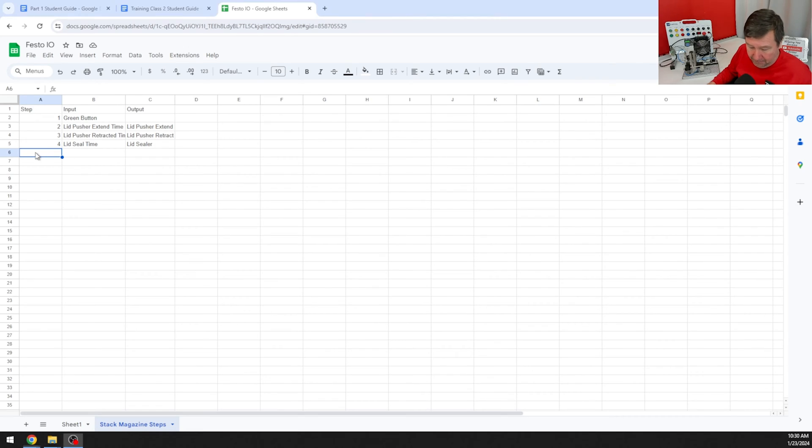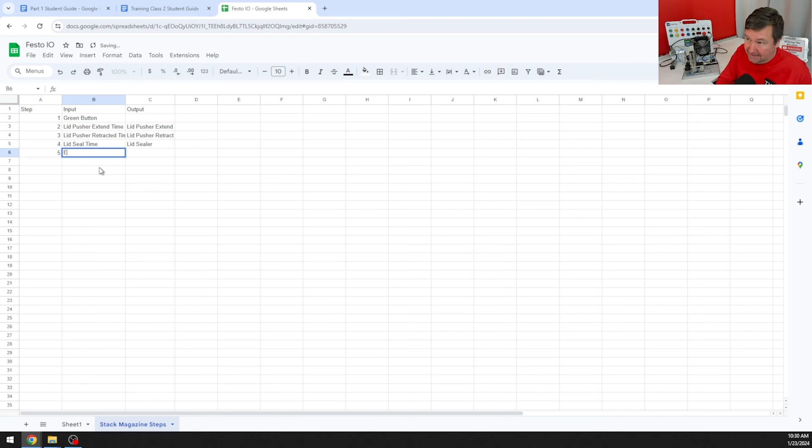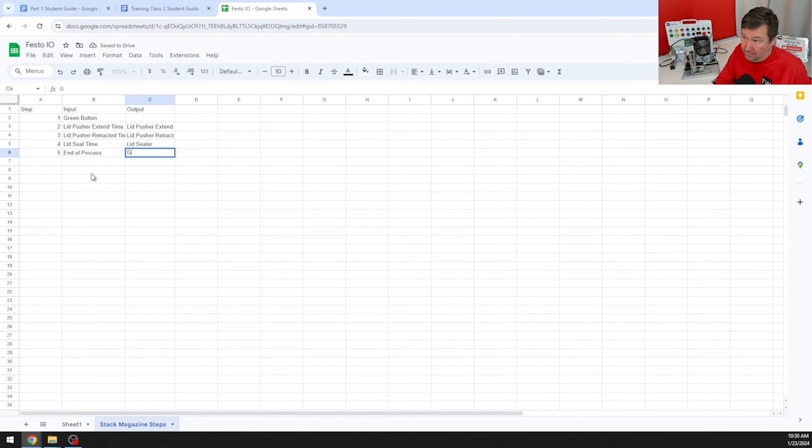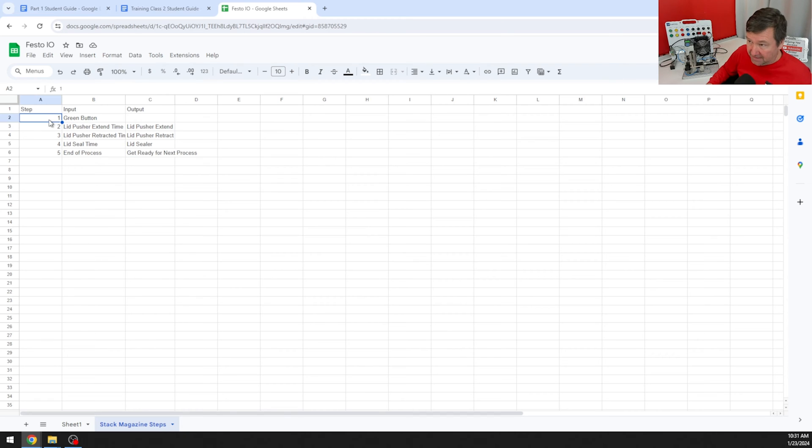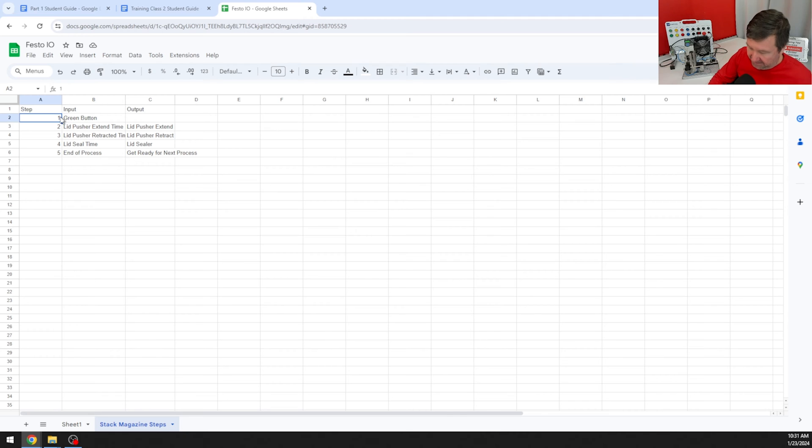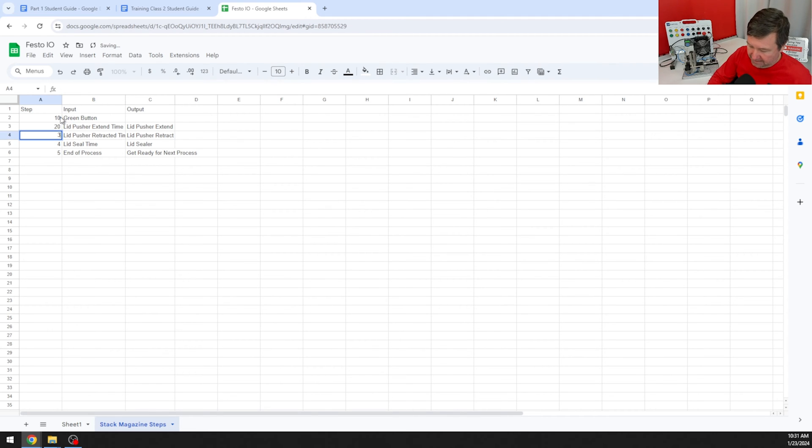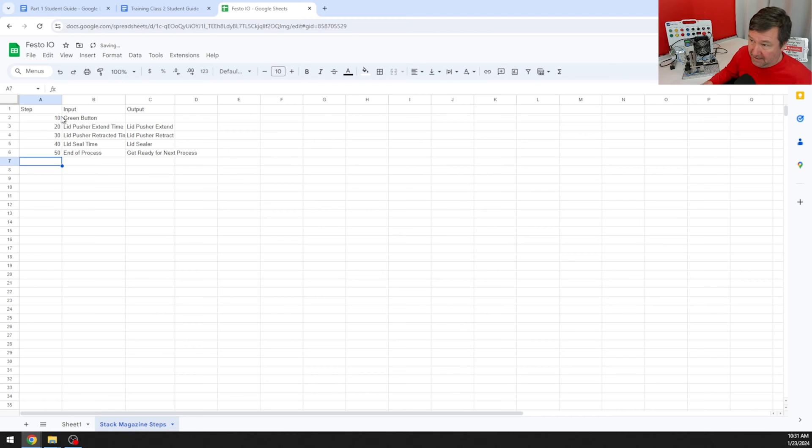Once it is retracted, now we need to push our lid presser down for a certain amount of time. Step four will be lid seal time, and we are going to extend our lid sealer. There's actually one more step - we do have a step five that needs to get us ready for the next process. Since we're skipping through so we have room to add, I'm going to make this step 10, step 20, step 30, step 40, and step 50.